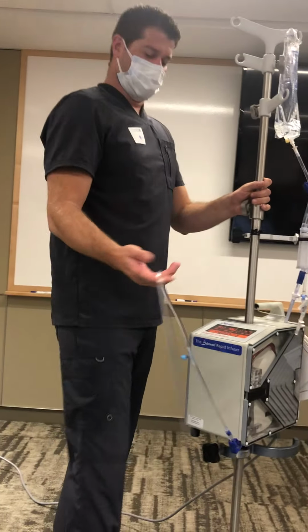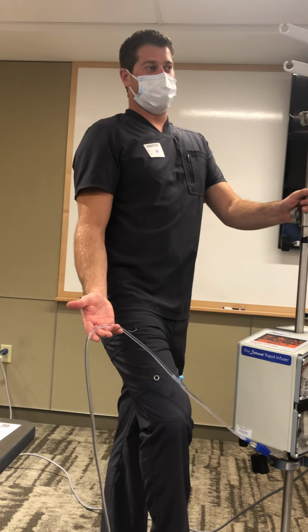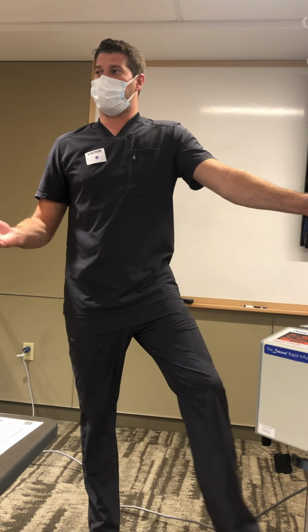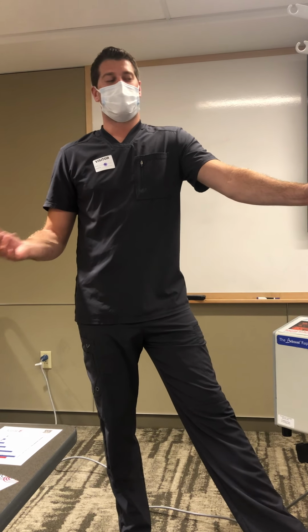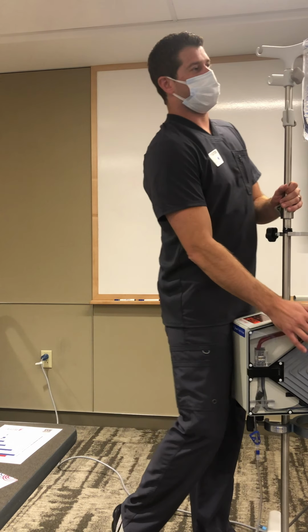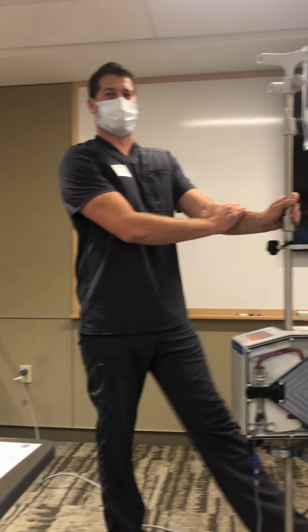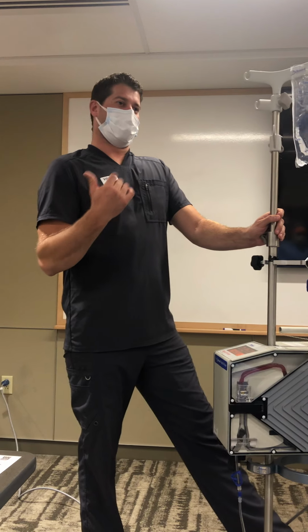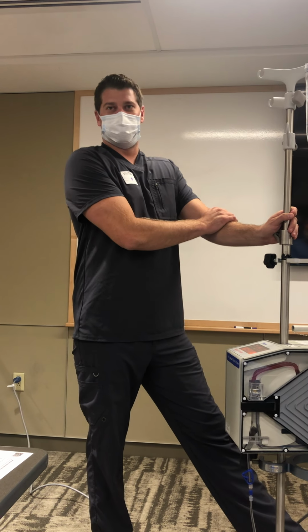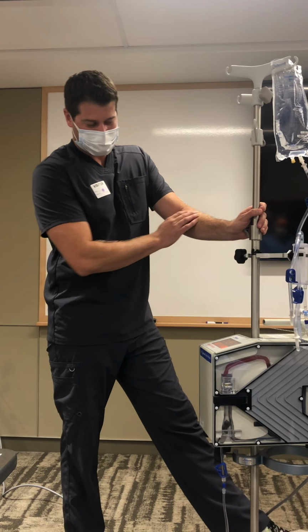Cryo's natural reaction when warmed is to stick to plastic. So you think you're delivering it to the patient, and in all reality, most of it's sticking to the inside of the tubing. So it's not that you're doing harm to the machine or the patient. You're just not doing any good, and it's wasteful. Platelets, we're a wheel pump. It beats them up, chews them up, basically renders them useless. So same concept. You're not doing harm to the patient, you're not doing harm to the machine, but it's useless and it's wasteful.